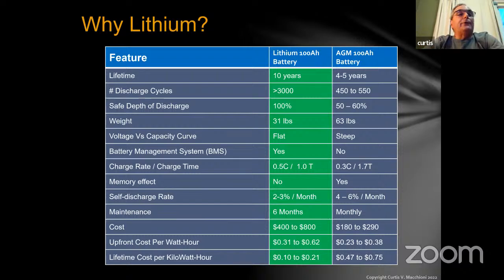Now, an AGM battery you really cannot discharge more than 50 to 60%, down to about 12.06 volts. If you go lower than that, you're going to damage the cells inside, and you won't get the 450 to 550 discharge cycles that are spec'd.